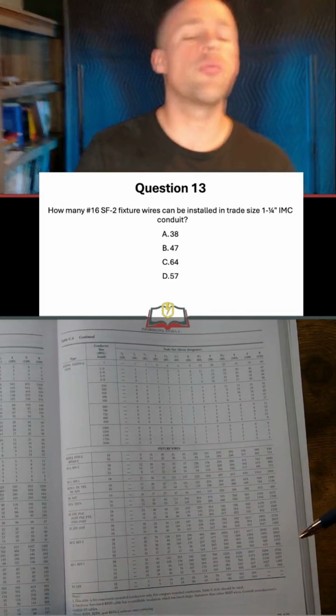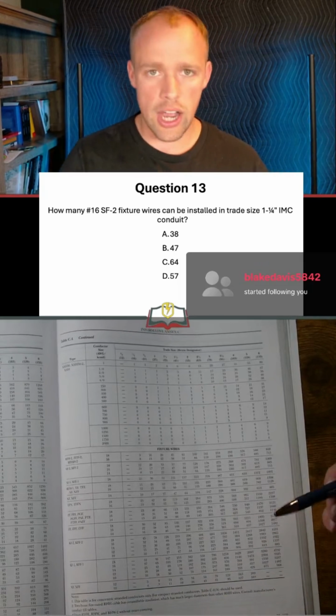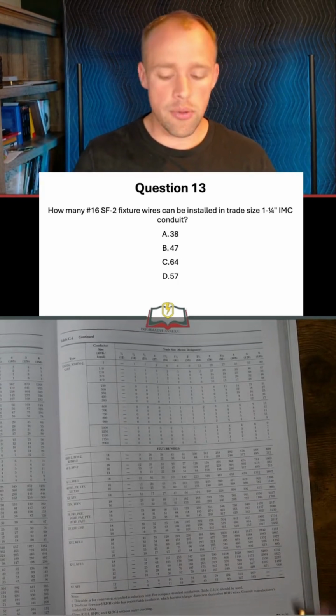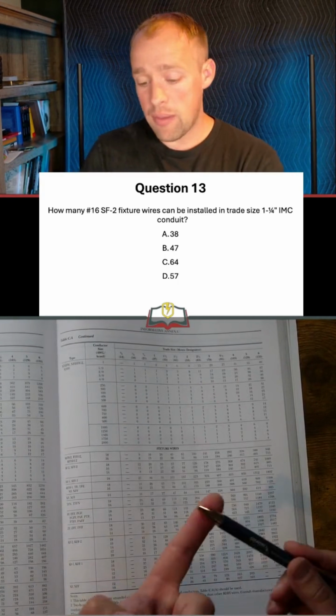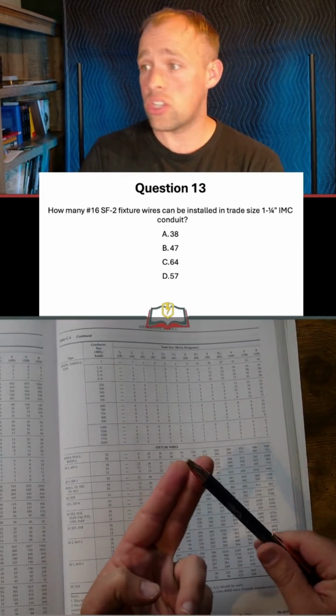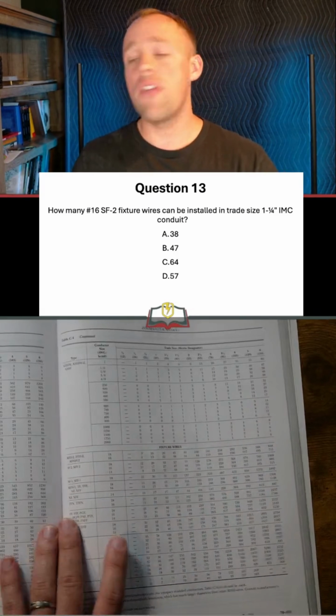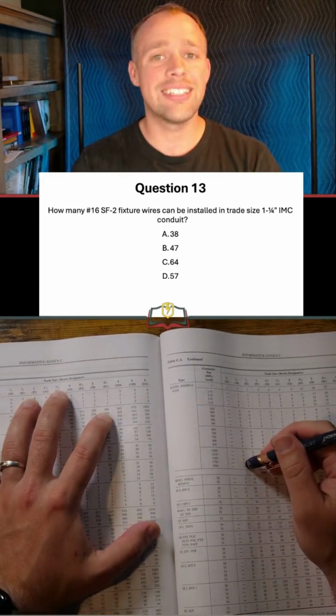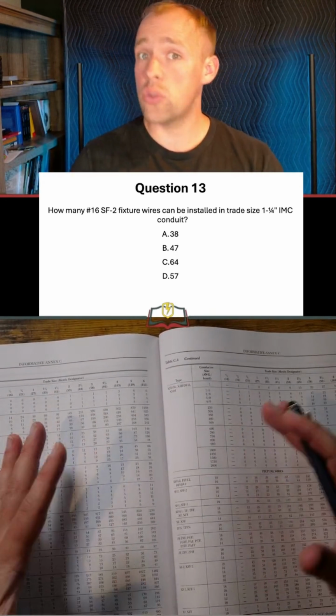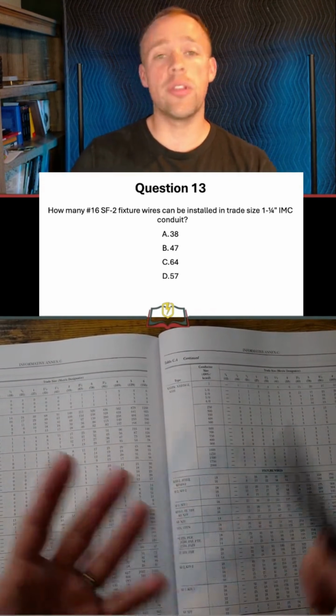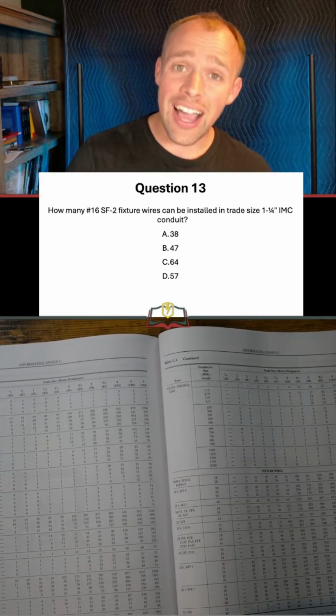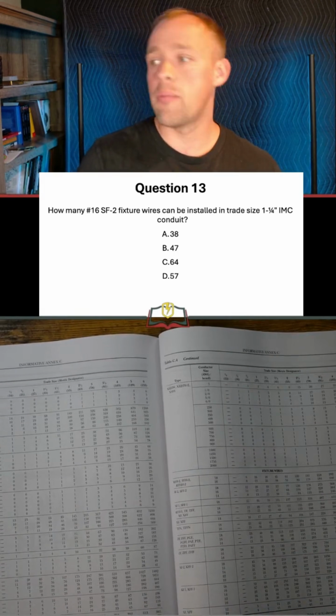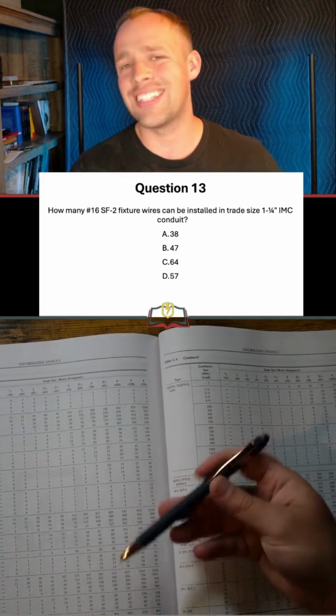Guys, remember, there are two different levels to conduit fill questions. There are the conduit fill questions where you have the same size and insulation, just like our question here. Anytime you have a question like that, you go to Annex C. When it's a more difficult question where there are multiple sizes and multiple insulations, we have to go to chapter 9, table 5, and then chapter 9, table 4, which I think we'll get to in this set of 10.